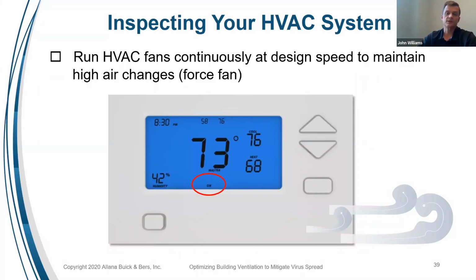Now, a concern there is if the outside air dampers are open while we're doing this, we're bringing in unconditioned outside air and mixing it in our building. So again, this is going to depend on where our location is. If we're in a high humidity area, we may want to make sure that even if we're running that fan, we're only opening the outside air damper whenever we're heating or cooling, so we're not bringing in high latent loads, high humidity into our building. But again, at that point, we're circulating more air through the building.